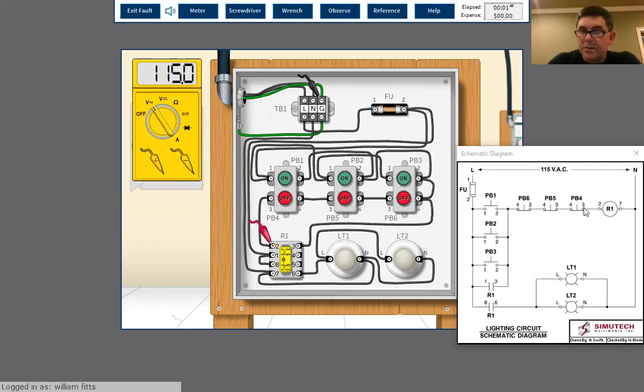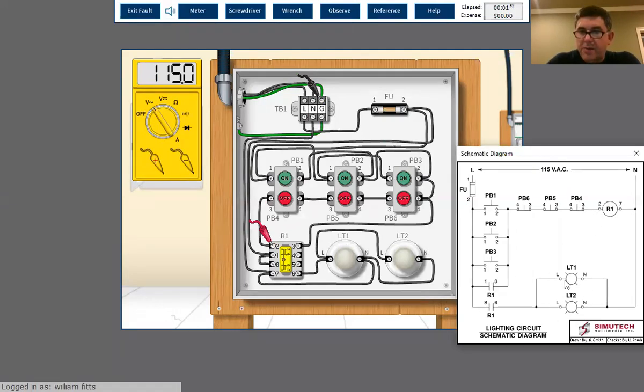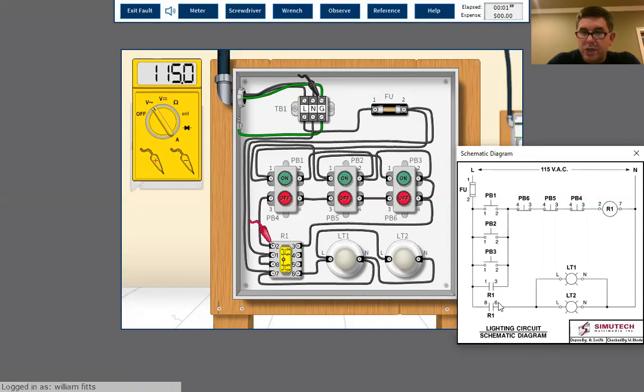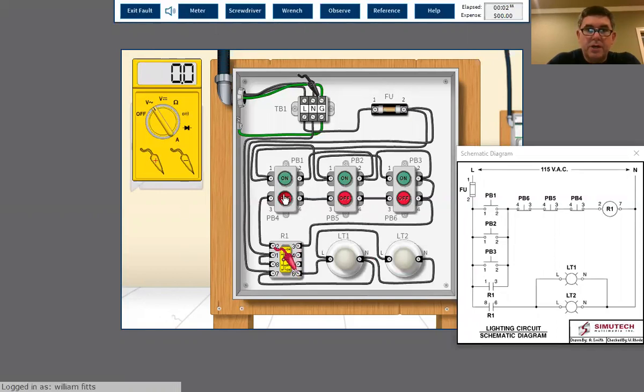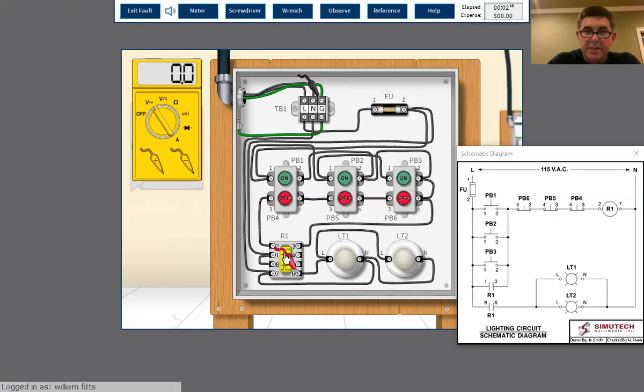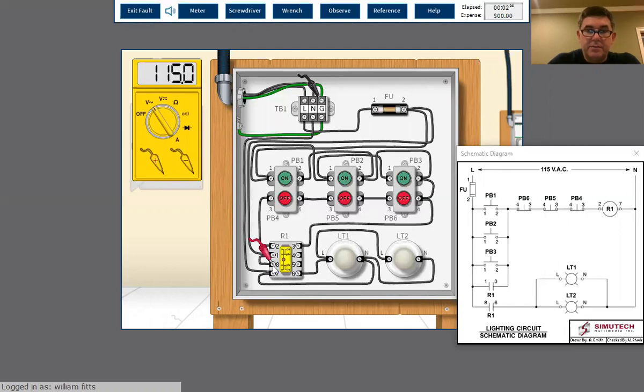Of course we know going in we're getting 115 volts. We know we're getting power to this point right here. So how come the light? The lights are coming off of the R1 relay terminal 6. Let's check it and see if we're getting power to the lights. So it is terminal 6, put it right there. Turn it on - nothing. So let's go back to the other side, which is number 8. Number 8 is good, right? But coming out is no good.